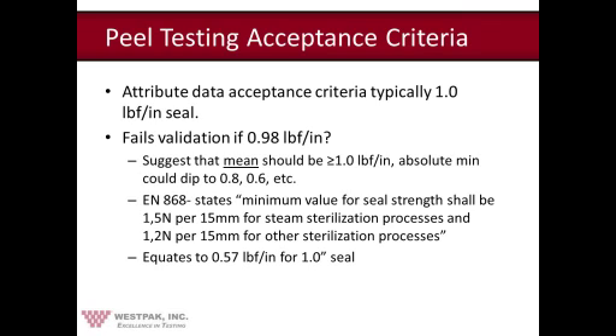Herb, do you want to add anything here? Those are really good points, Nora. We also find that not only a minimum strength in the seal area is important, but also a consistent strength is very important. I mean, if you're just looking at minimums, you could have 15 or 20 pounds per inch, but the simple fact is that you couldn't get the darn thing open in an area, let's call it a sterile field, where this product is being dispensed.